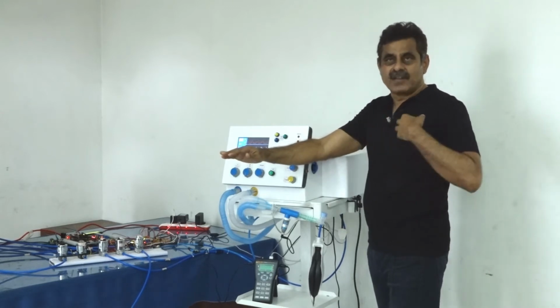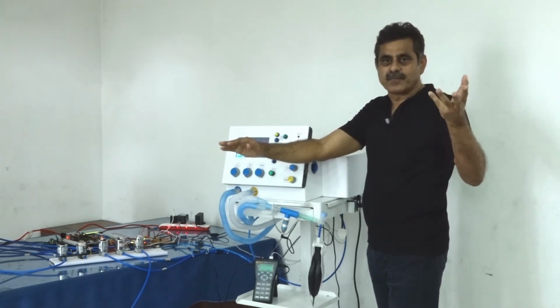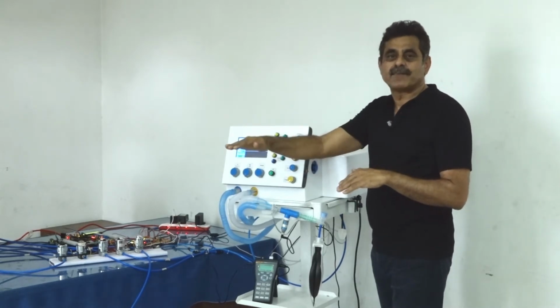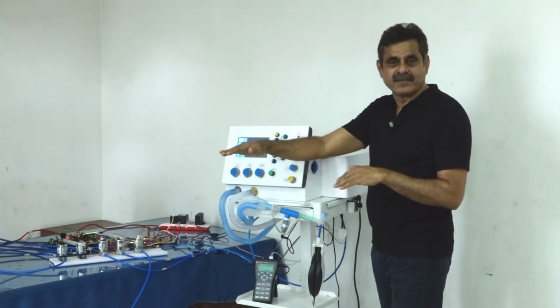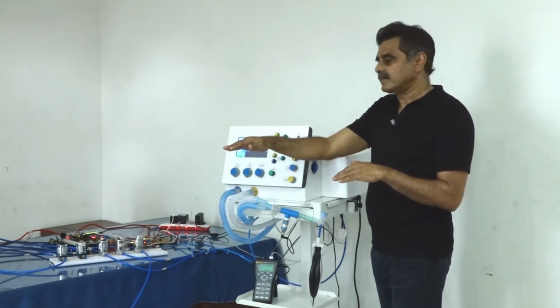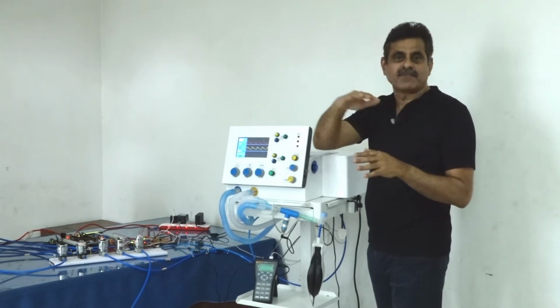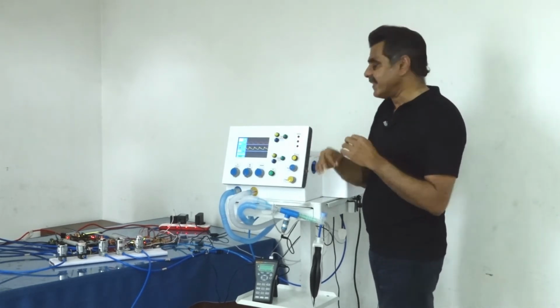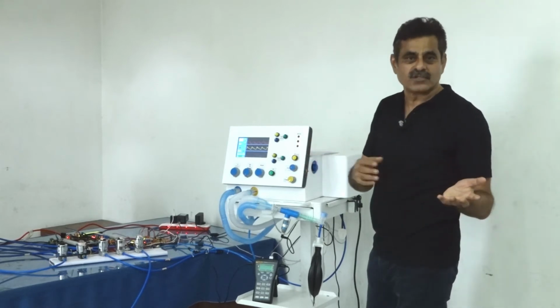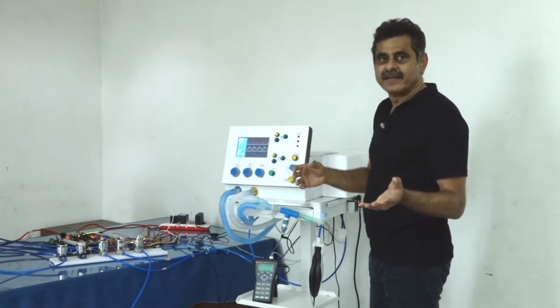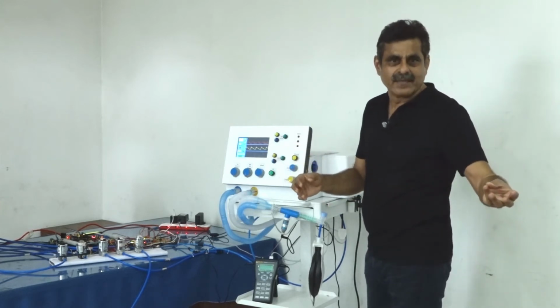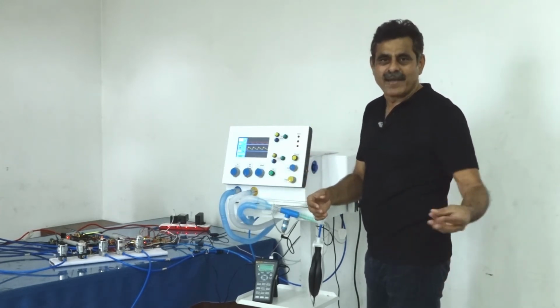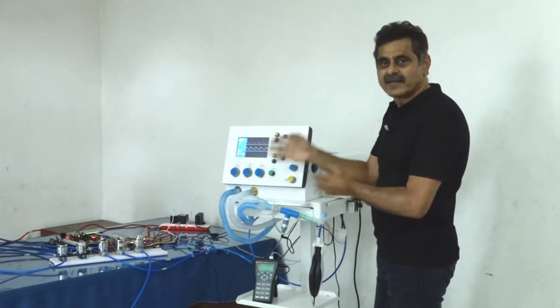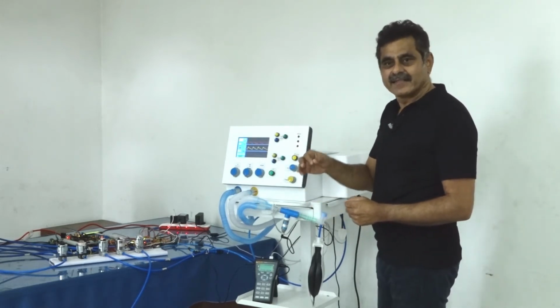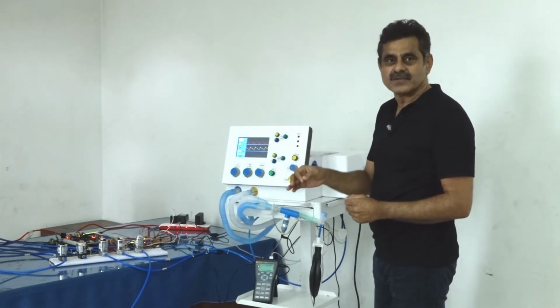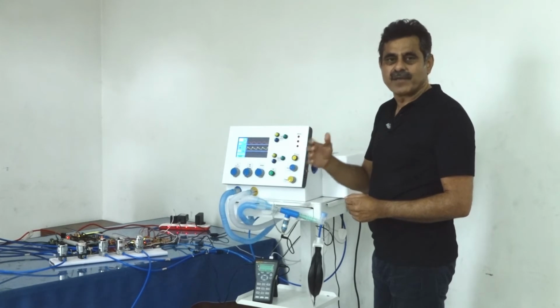Normally we exhale to atmosphere, which is neutral or zero pressure. But COVID patients have to exhale against positive end expiratory pressure, PEEP. All these three pressures and the shape of the waveform are very, very critical. That is what ICoVent can do, and what most of the other mechanized ambu bags cannot do, so doctors cannot use them. Ambu bags can be used in an ambulance or in transport, but not as an ICU ventilator. And the shortage is going to be in the ICUs, if the cases increase, and that's what we are bracing for.